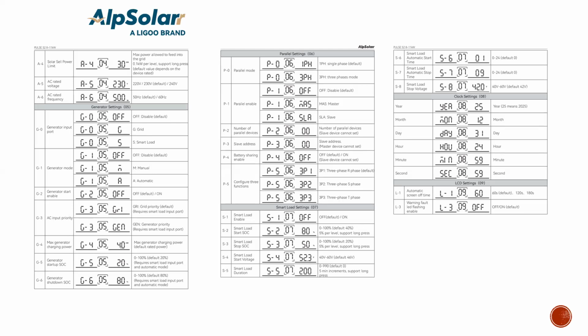The P0, the first thing you are seeing there is parallel mode. Are you parallel in a single phase or three phase? You choose whatever phase you are doing, and then you set which one is master. Then you set how many of those systems you are connecting in parallel. Is it 4? Is it 3? Is it 6? Is it 9? P2 is where you choose the number of devices in parallel. P3 is where you choose the slave address.